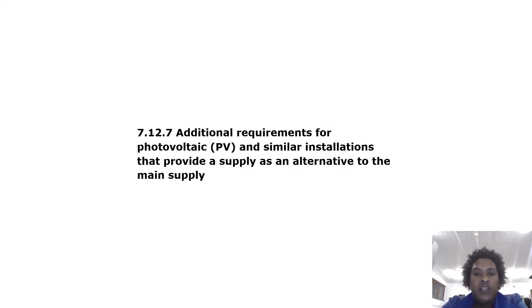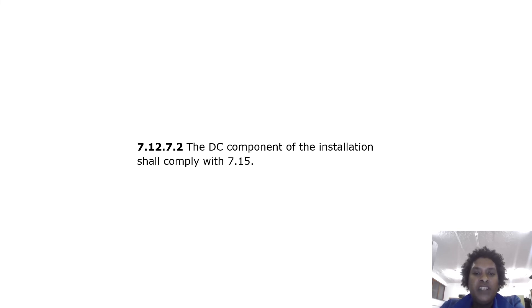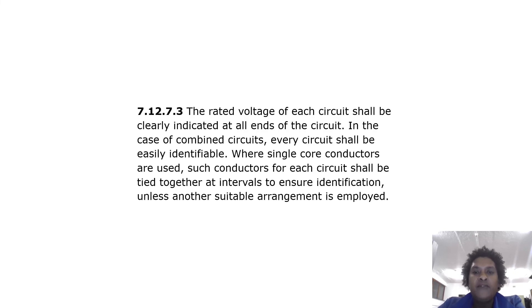Additional requirements for photovoltaic and similar installations providing a supply as an alternative to the main supply: the PV installation shall comply with SANS 60364-7-712, and the solar panel shall comply with SANS 61215 for poly and monocrystalline, or SANS 61646 for thin film. The DC component shall comply with 7.15. The rated voltage of each circuit shall be clearly indicated at all ends of the circuit, and in combined circuits every circuit shall be easily identifiable. Where single core conductors are used, they shall be tied together at intervals to ensure identification.